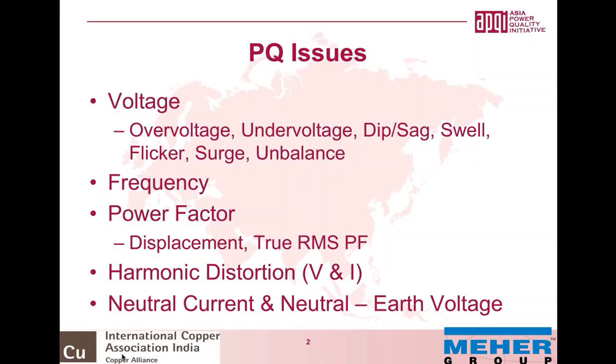And traditionally, it is a well-known fact that if there is an unbalance in the system, the resultant current will flow in the neutral. But there is another problem that has emerged, particularly in the last 10 to 15 years, where the IT companies' primary loads are in the form of SMPS loads, which are servers, and these generate particularly triplen harmonics.